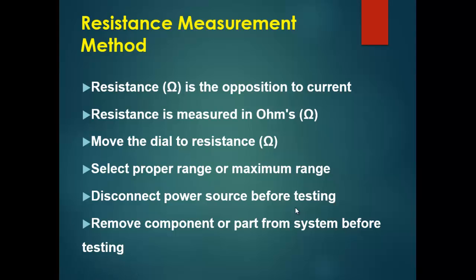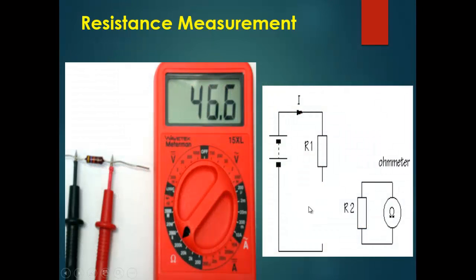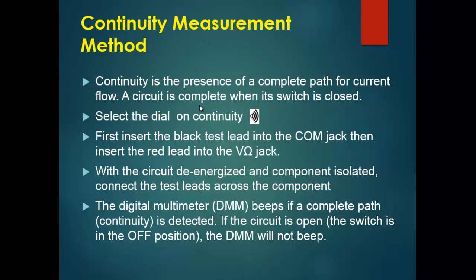Never test resistance in an energized circuit. It is always better practice to remove the component from the board to properly measure its resistance. As you can see in the picture, we first disconnect resistor R2, then select the dial on ohm, select the proper range, connect both probes across the resistance, and the meter shows the resistance value.